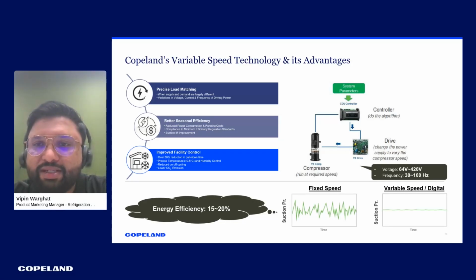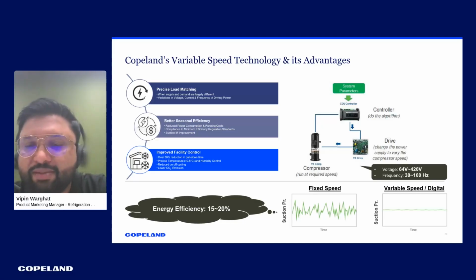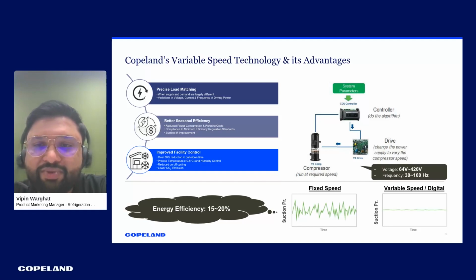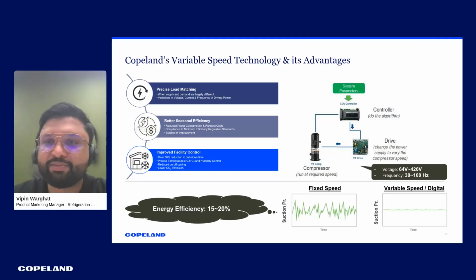So the variable speed compressor, which is equipped with a variable speed drive, stabilizes your suction pressure. Because you are able to stabilize the suction pressure, you are able to maintain the right temperature with a difference of -0.5% from the set point. And because of the variable speed, you are able to manage the demand and supply gap. Whatever you need, only that much refrigeration will be delivered. So this variable speed solution by Copeland is able to deliver around 15 to 20% of energy efficiency overall.